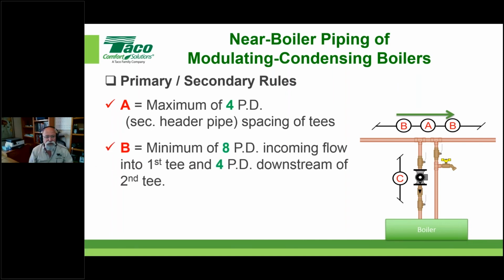Of course, that leads us to the B note. I've got an arrow here to show what I'm talking about, from here going left to right. Now the minimum amount of pipe diameters is 8 coming into this first T - we'll show you more detail on that in the next slide. But here's the concept and the rule: the minimum is 8 pipe diameters of this secondary pipe.